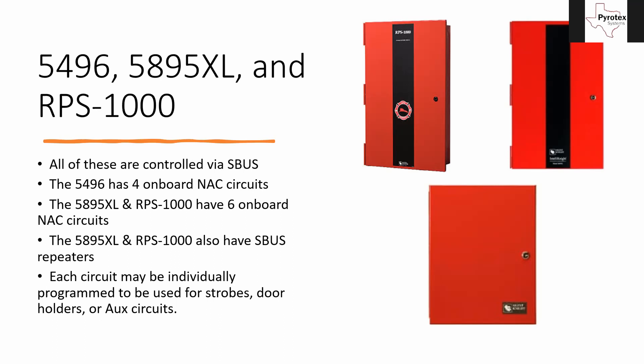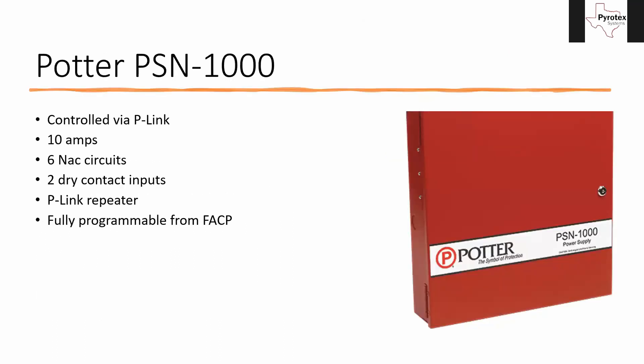The last power supply I want to talk about is the Potter PSN-1000. This is a 10-amp unit controlled over P-Link, which is just like SBUS. There are six NAC circuits on it, it has a P-Link repeater just like the other six-circuit Silent Knight panels, and it's fully programmable from the FACP. One difference from the Silent Knight panels: it has two dry contact inputs — kind of like built-in monitor modules, which is neat. We don't do a lot of Potter systems, but if you ever run across one, there is an intelligent power supply for it.